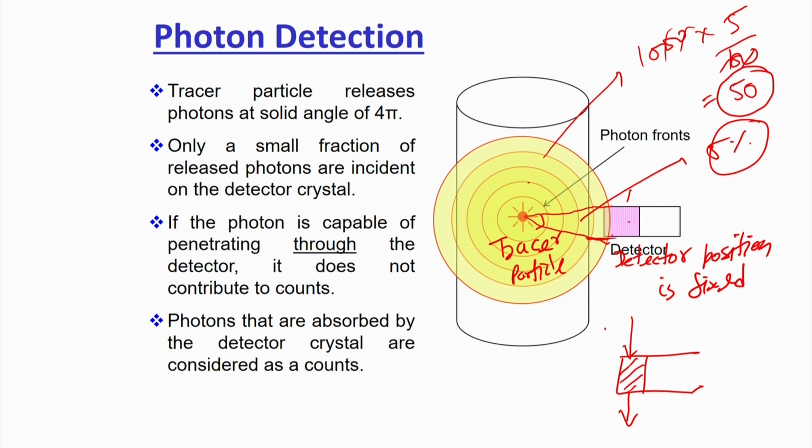If it does not get absorbed, then it will not transfer energy to this crystal, and the crystal will not go to the excited state, and while coming back it will not emit a photon or photoelectron. So in that case there will be no signal generation. As I mentioned about how the detector works, it goes to the excited state, emits a photoelectron, which goes to the cathode and is converted to an electron, then it moves through the proper dynode circuits to the anode to give a pulse of the current, and that is the pulse of current we measure.